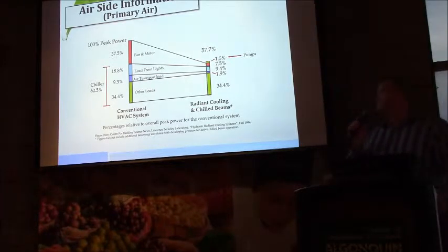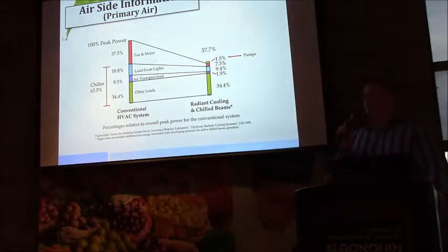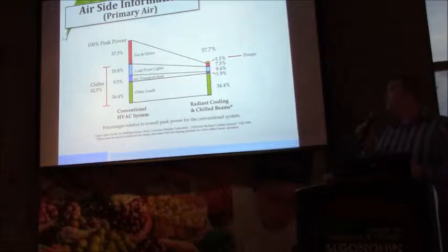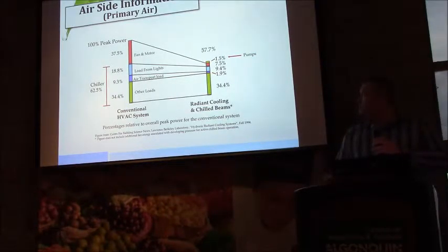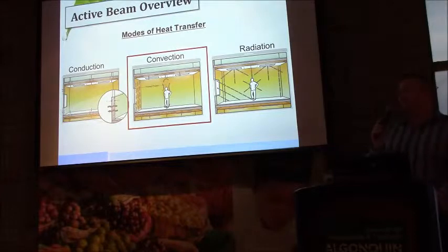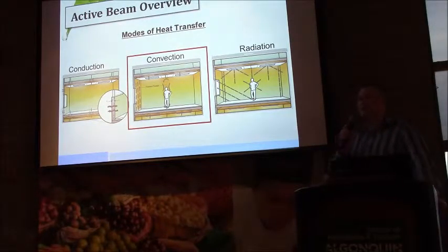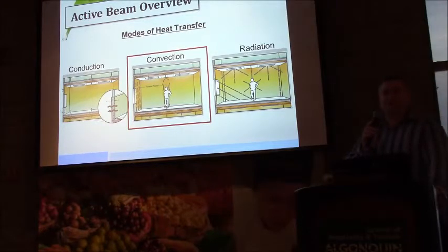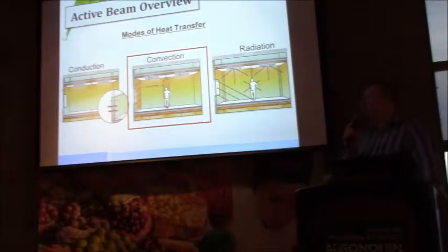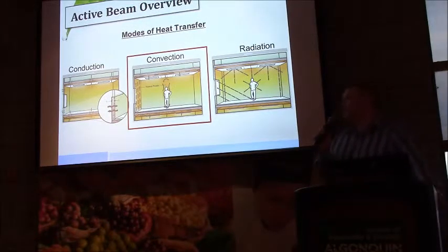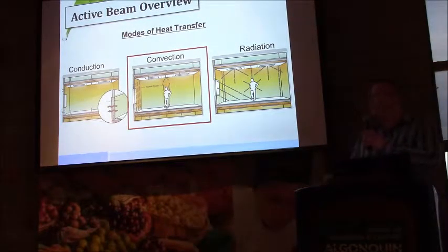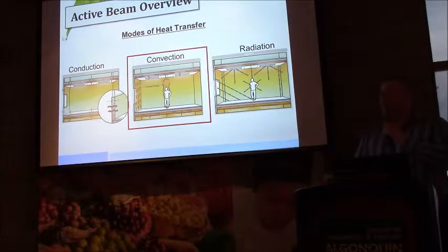This is a graph that shows principally where the energy is being saved, and obviously reducing the total airflow in the building envelope will reduce the total energy consumed at the fan. And an active beam is a fully mixed system. There's no radiant effect associated with an active beam. The air is mixed in the space very thoroughly. Ventilation effectiveness of an active beam in cooling is typically unity. So a VE of 1 for beams in cooling, and can be also true for beams in heating, but there's some restrictions in terms of the application of beams in overhead heating to ensure that we get proper throw and drop in the space.